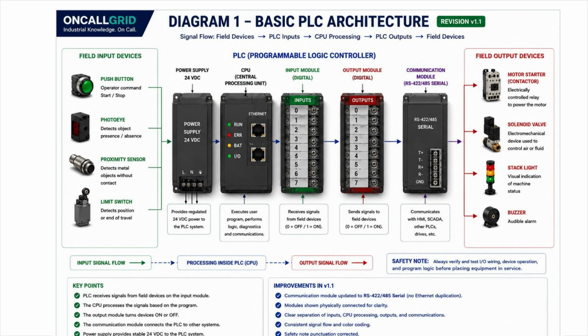Let's walk the hardware left to right because this order matters. First, power supply, 24 volts DC. That's what feeds the whole system. Next, the CPU, the central processing unit. This is the brain. It executes your program, does the diagnostics, and handles communications. Notice it's got a built-in Ethernet port right on it. That's how it talks to an HMI, SCADA, or other PLCs on the network.